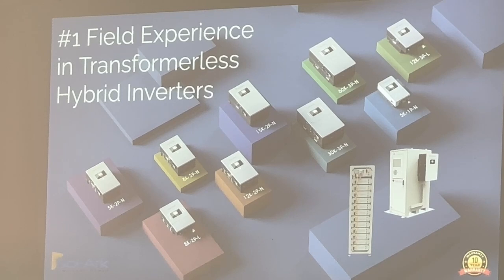So, 2-pole. We're used to thinking of single phase, right? In Europe, West Africa, China, you have a neutral wire which carries no voltage — that's your return — and then a single live wire at 230 or 240 volts. So when Sol-Ark, an international company, advertises their inverters as single phase, the 2P means two phase, 2-pole. So you have 2 live wires and a neutral in between — the neutral is at 0, and you've got 120 and another 120. That's split phase, 2 phase.